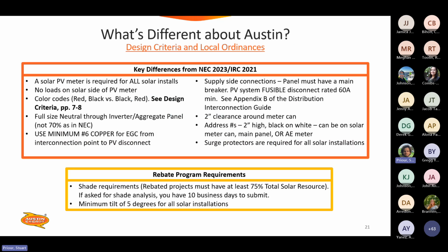So what's different about Austin? Maybe most importantly, we have a solar PV meter, which is required for all solar installations. There is a newly published list of approved meter sockets, which you should reference. You can just search Austin Energy approved meter sockets, and it should be the first link that you find.